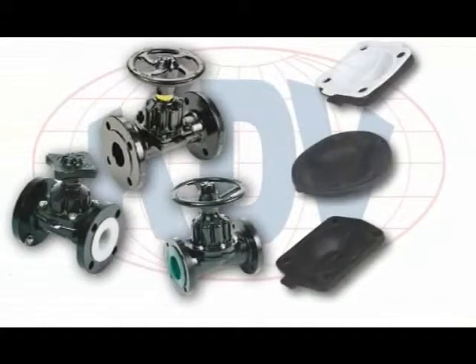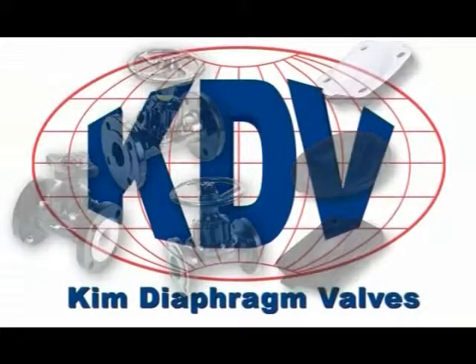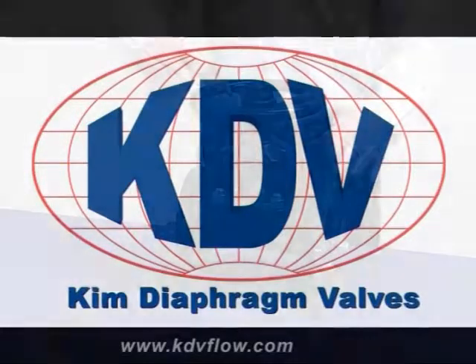KDV diaphragm valves are supplied with over closure protection as a standard feature. Correctly setting the over closure will ensure that the diaphragm is not subjected to undue pressure, increasing diaphragm service life and reducing valve maintenance.